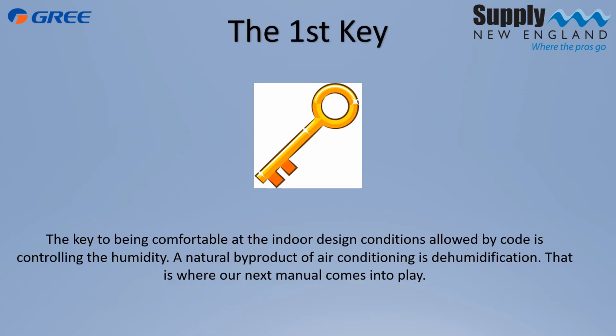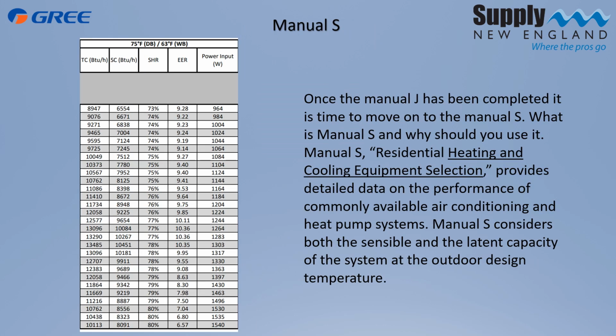Now, keys. The first key about remaining comfortable, as I said before, is controlling humidity. A natural byproduct of air conditioning is dehumidification. And that's where our next manual comes into play. It's called the Manual S. The Manual S uses our exact locations, our exact design conditions, to tell us how our system is going to perform in that location. It's called the Manual S because AHRI is rated on a 95-degree outdoor temperature. We've already learned that in Laurel's Mass, that is not our design temperature. It's only 88 degrees. So let's see what our system will do at 88 degrees.